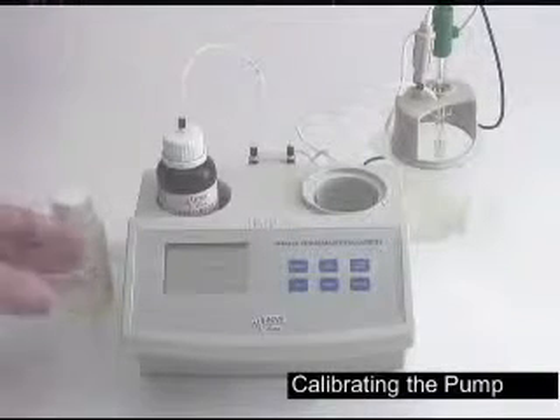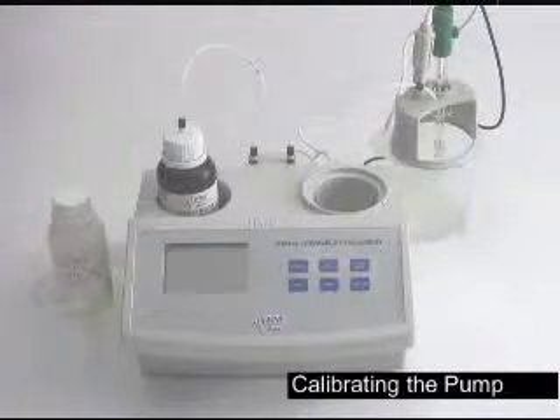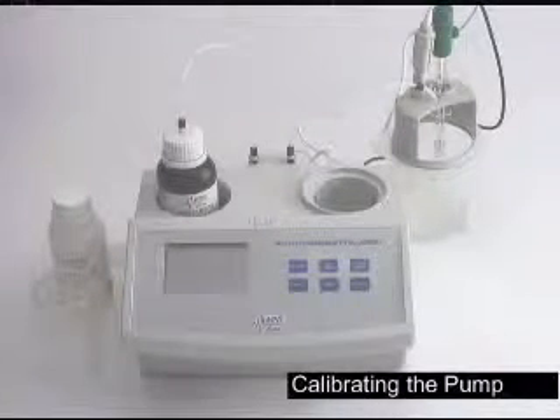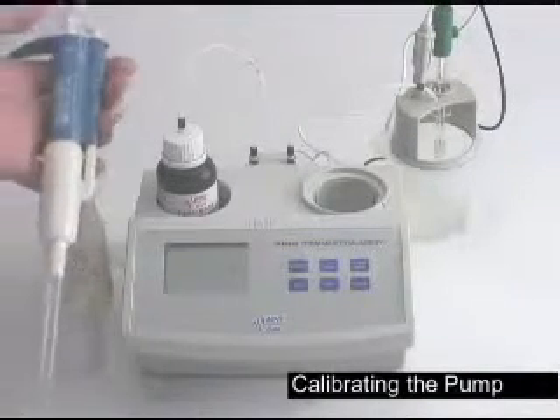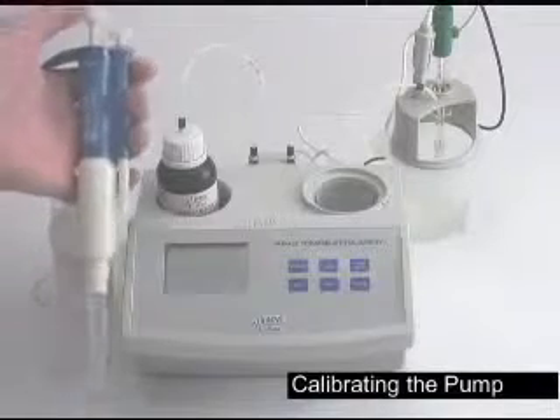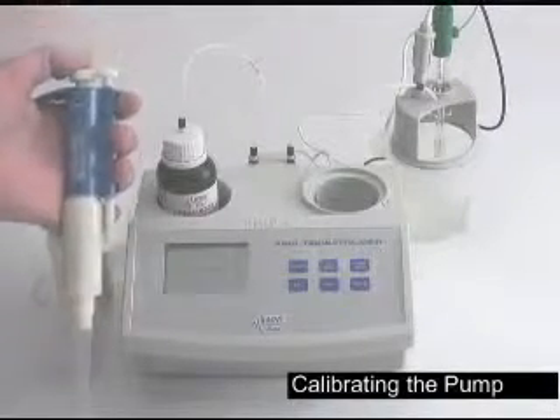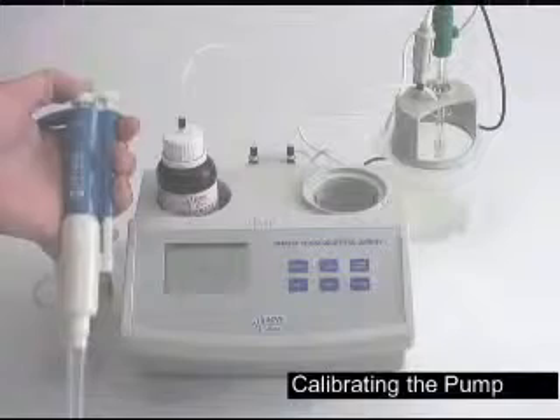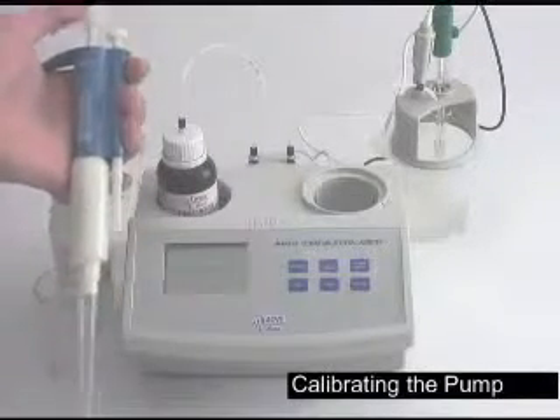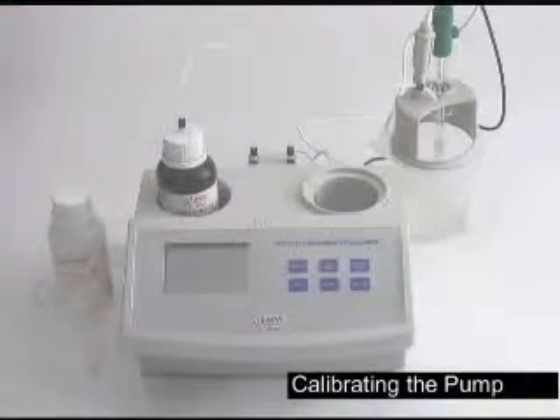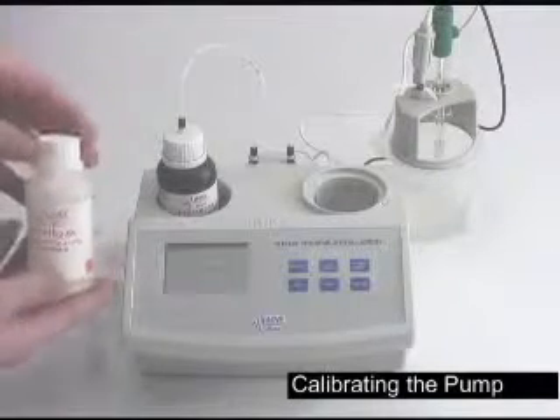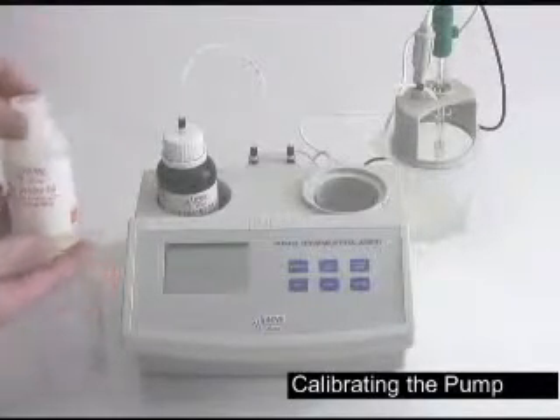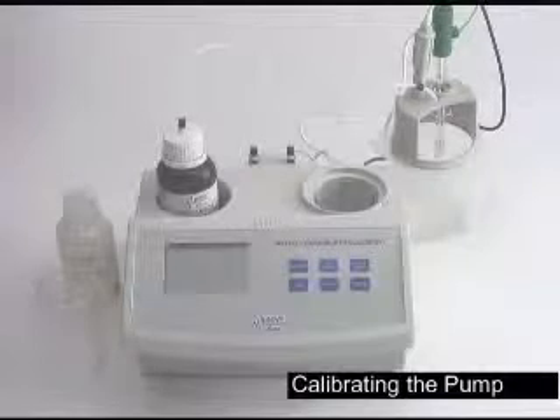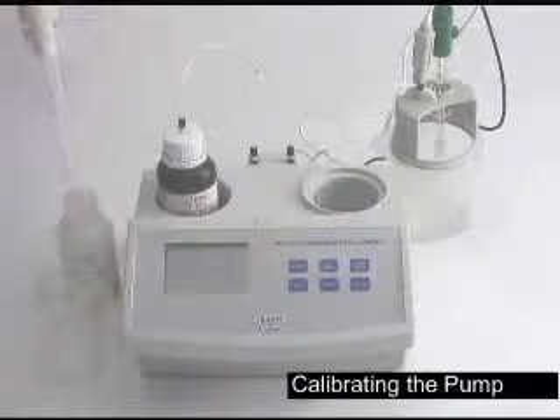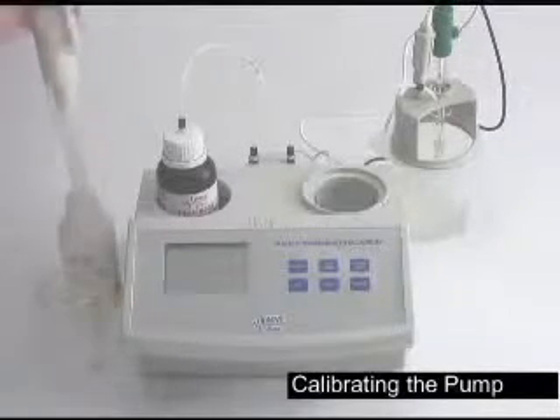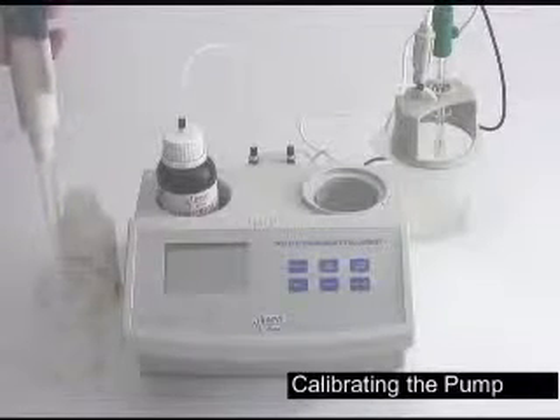We're going to take a clean beaker, add the stir bar, take the auto pipette that was provided. This is a 2-stage pipette. And you go down to the first stage, put it into your titrant, lift it up. When purging it, you'll use the second stage. Take the 84102-55 standard. Again, first stage. Place it in your beaker.